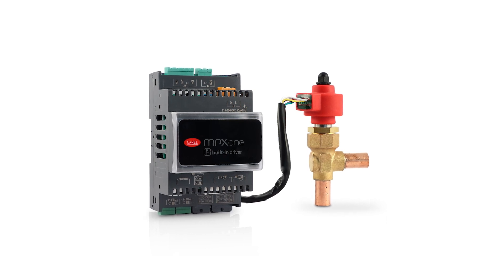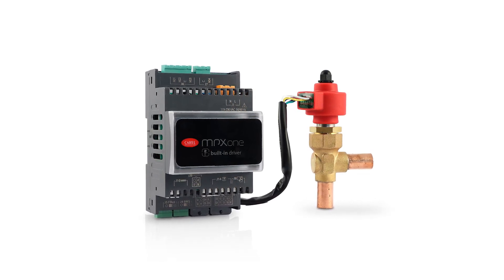Alongside the consolidated MPXone solution, the offering has been extended with the introduction of the MPXone Advanced version. This latest generation device integrates the management of a unipolar stepper valve or, alternatively, a generic modulating valve via 0-10V signal.